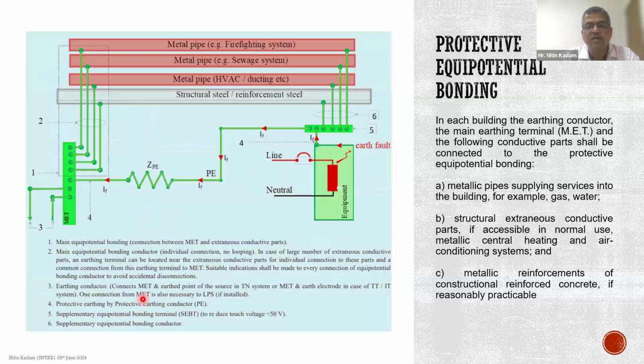This is how the protective equipotential bonding is further elaborated. In this case, you see here, the structural steel or the reinforced steel is connected to the main earthing terminal. The metal pipes of the HVAC are connected to the main earthing terminal. The metal pipes of the sewage system, the firefighting system, or the water supply system are connected to the main earthing terminal. And at the equipment level, they are also separately connected to this with metal conductors.